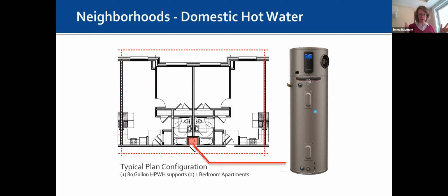So much better from an energy perspective, because we're talking about net zero, right? How can we get our usage down? So here's a really great opportunity. We've done a lot of these. These units require air circulation around them. One of the big issues initially was, how do you put it in a closet? Because you need air around it. You can't just stick it in a closet and close the door and hope for the best. It's going to subcool in that space. You need ventilation around it, so you need to duct it out or duct it in, or put it in a larger space.